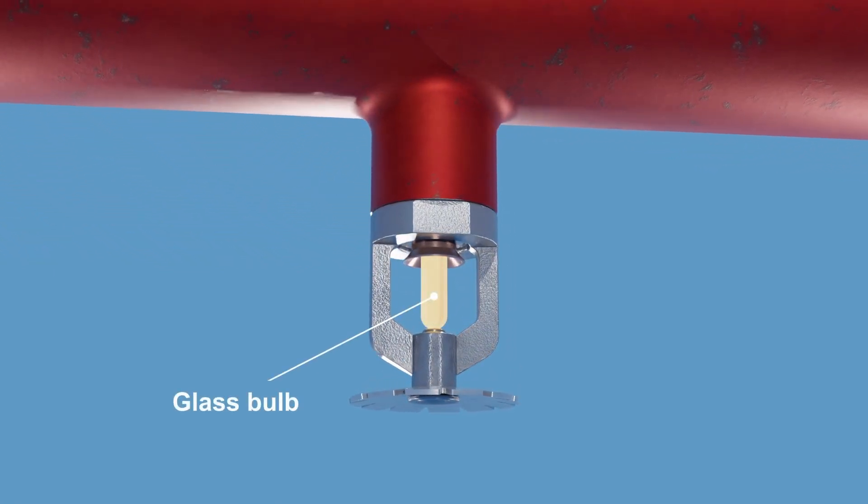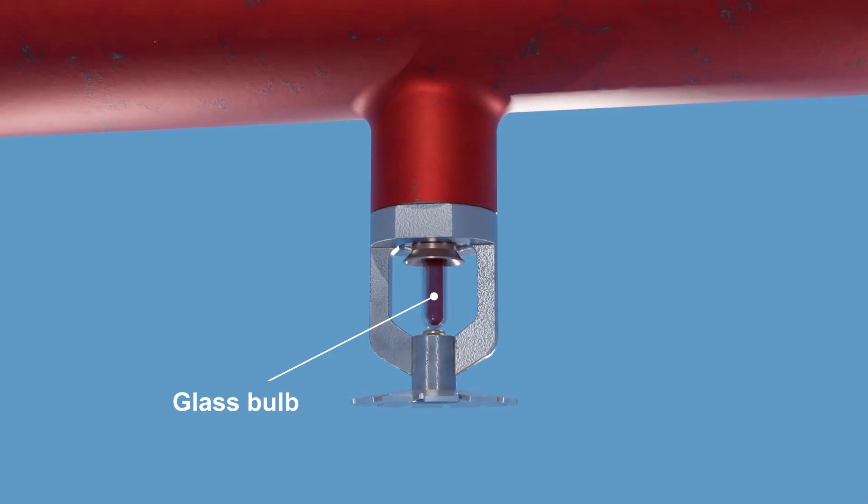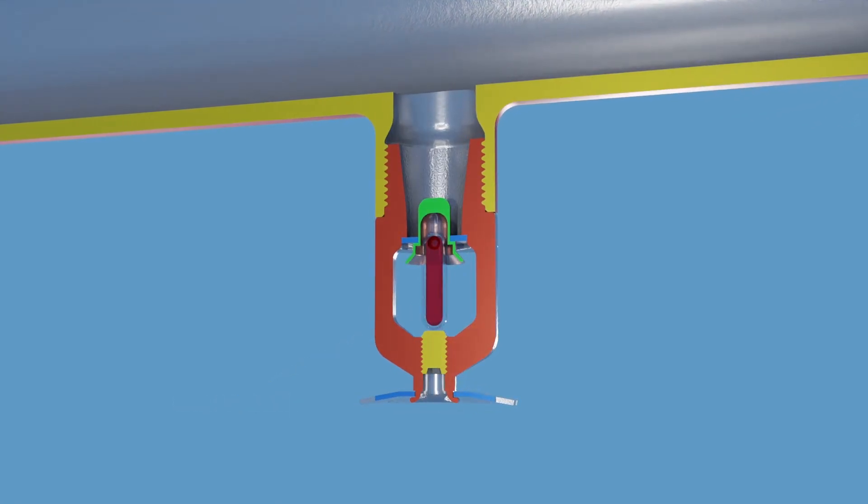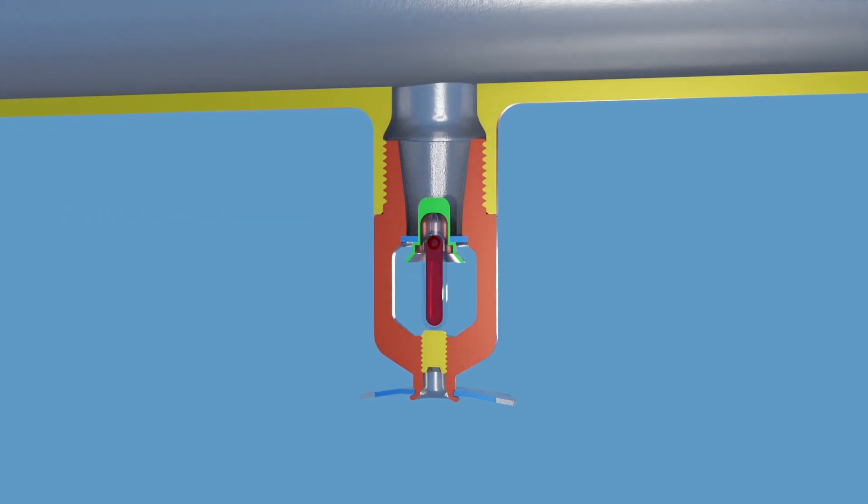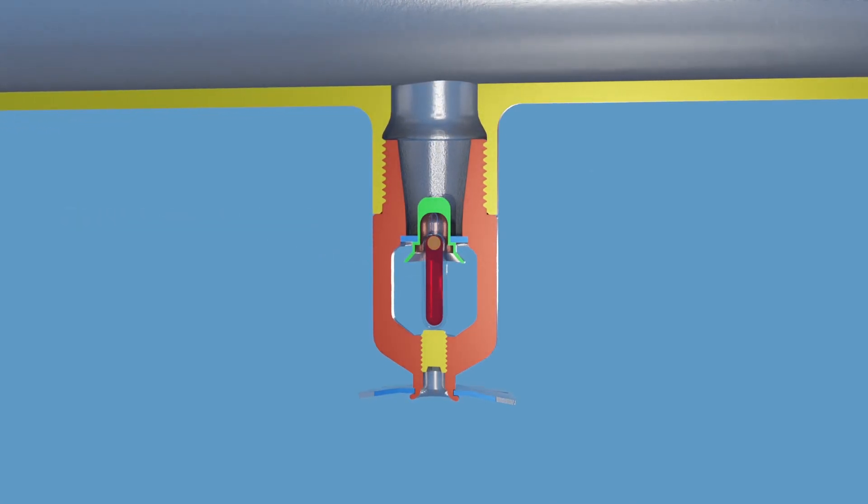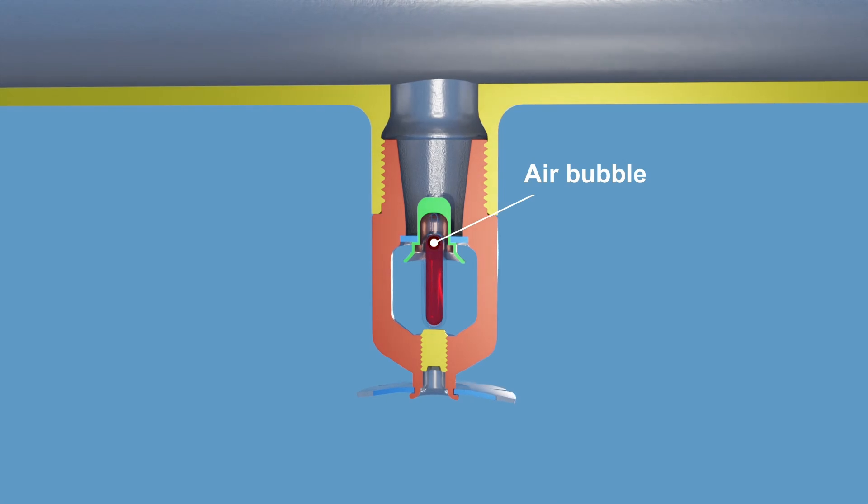This is the glass bulb, the active element of the sprinkler head. The bulb is filled with a glycerin-based liquid that expands when heated, causing the bulb to break at a certain temperature. Inside, there's an air bubble to allow for some expansion of the liquid without immediately causing the bulb to break.